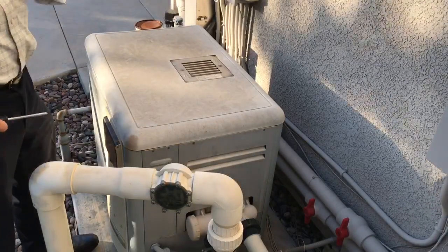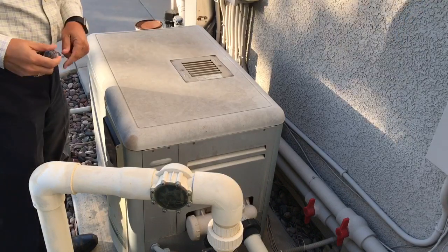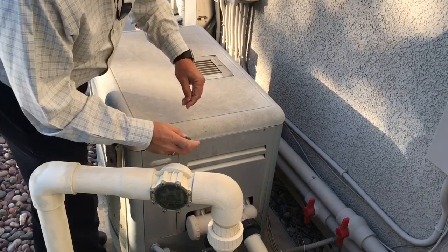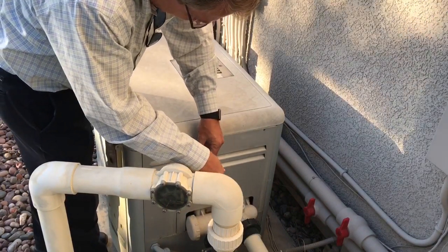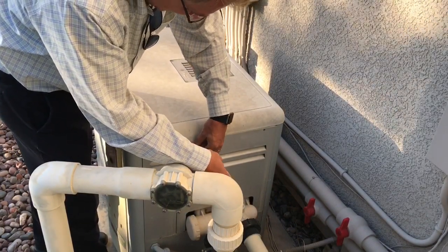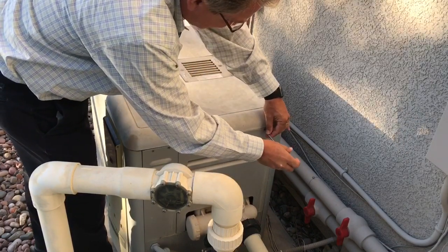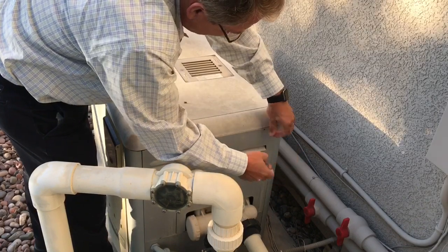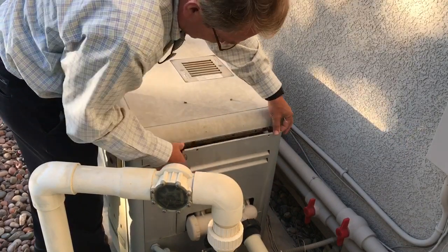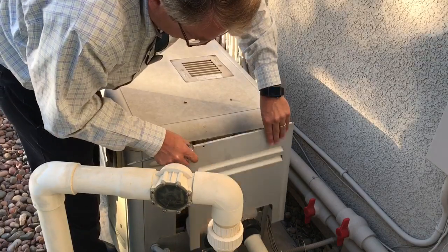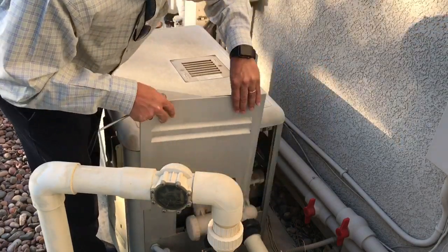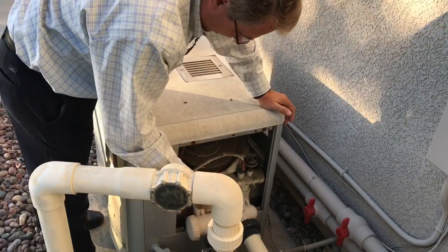So what I'm going to do is show you how to get in here to check some of the electrical that's associated with the E02 error. First, I'm going to take off this panel, and right behind it, you're going to see a bunch of switches. And one of the parts that I originally changed was a thermistor. Like I said, on YouTube I found a video, and it talked about basically this thermistor. So you have to take this panel off, take the two screws off, put this aside, and the thermistor was this part right here.